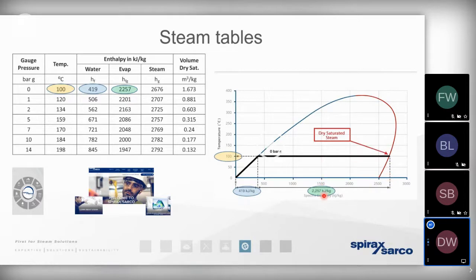So when we've added 2257 kilojoules to 419 kilojoules, we have then got dry saturated steam. And we've mentioned in previous presentations that dry saturated steam is critically important whenever we're sizing heat exchangers or calculating the rate of heat exchange for the process. As we've mentioned, we've got a number of issues caused by steam that is not dry and is not saturated with energy. In other words, with wet steam.